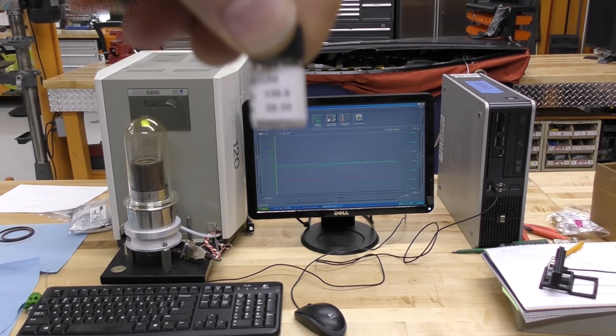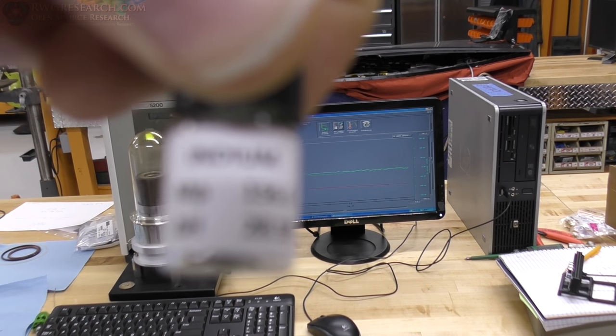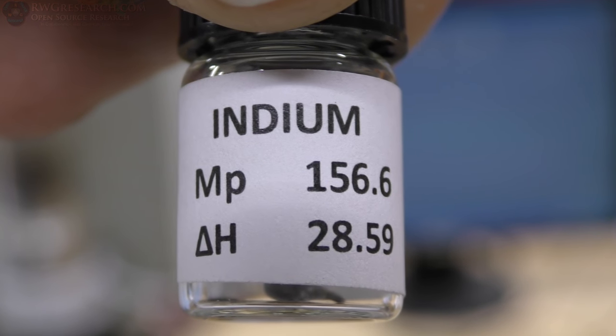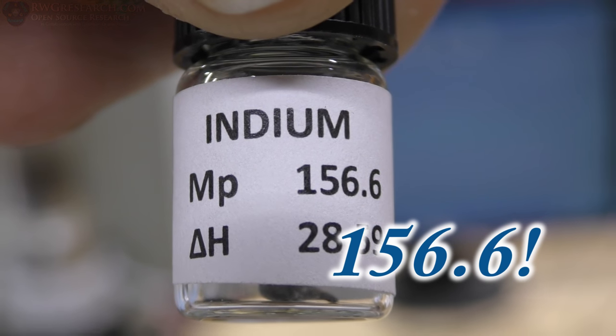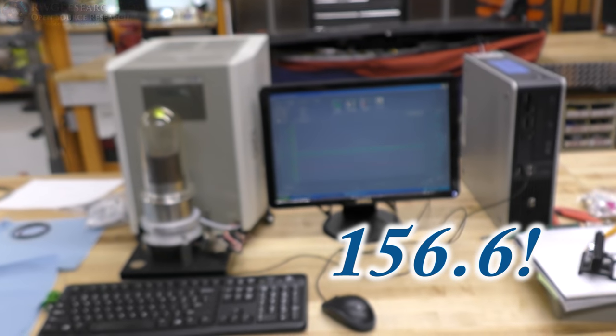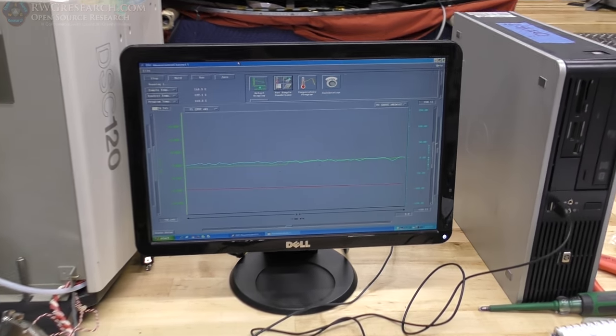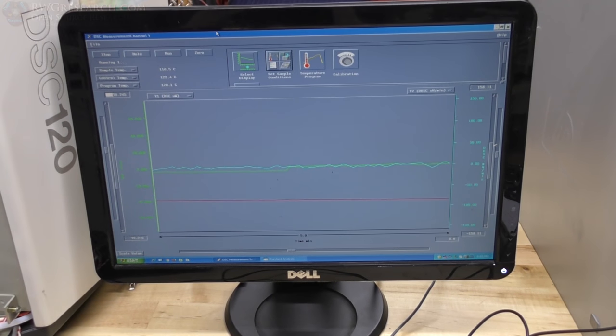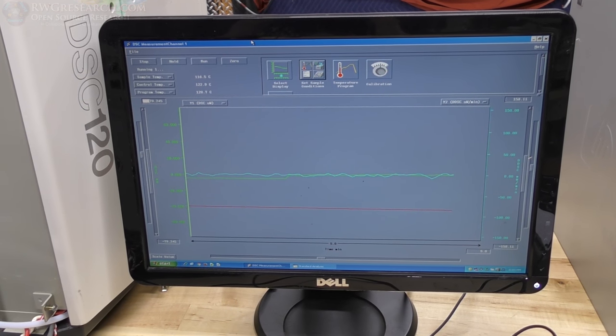So I've got a piece of indium in there, as you can see right here. So this piece of indium melts at 156.6. So on our graph here, we will check it and make sure it's accurately changing in the right spot.